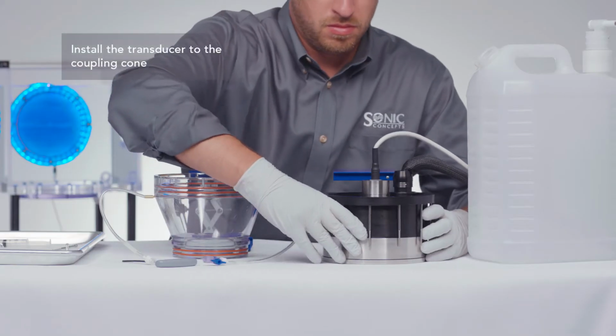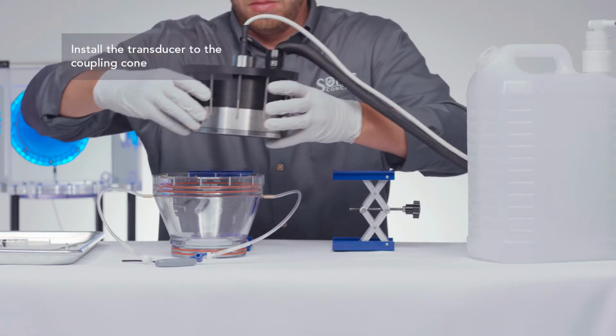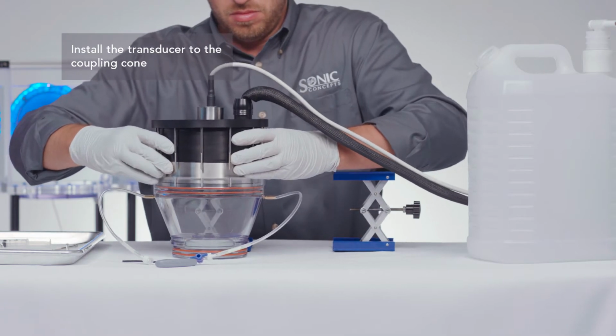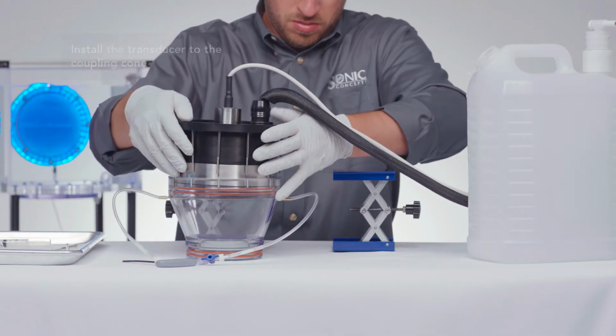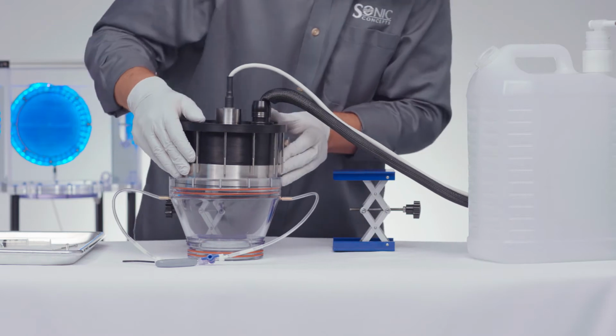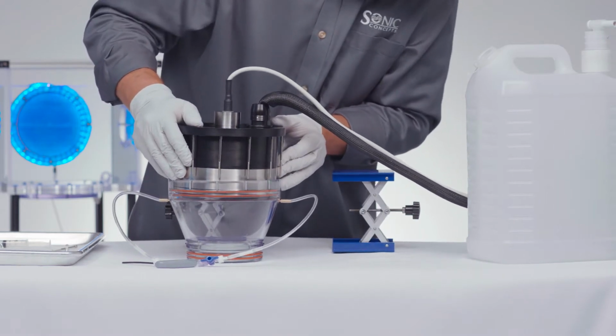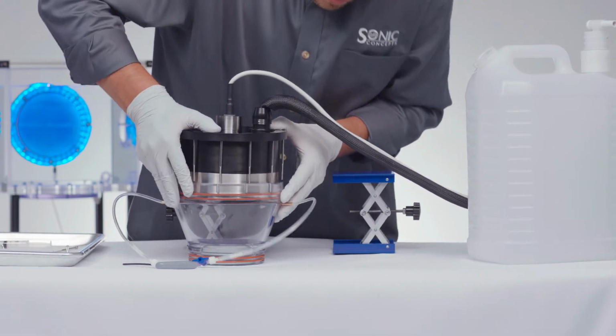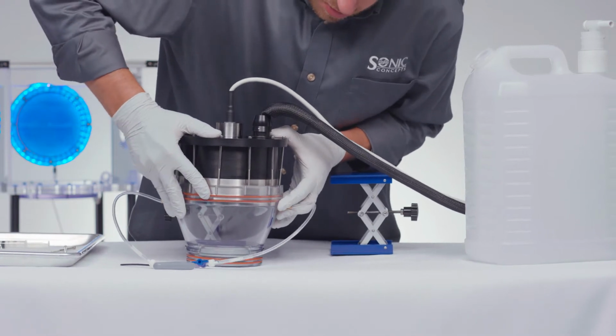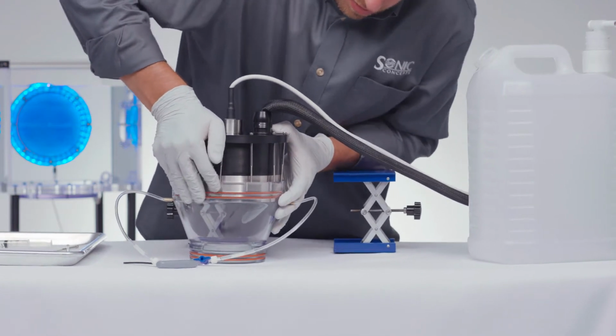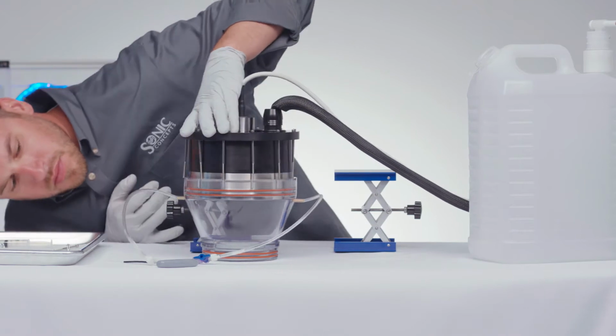Insert the transducer into the coupling cone with the transducer's radiating surface faced into the cone. Be sure to align one of the 12 screws to the same plane as the 2 exiting cables. Then align the in tube to that same plane and exiting as shown. Press the transducer evenly into the coupling cone until it bottoms out. Check screw alignment.